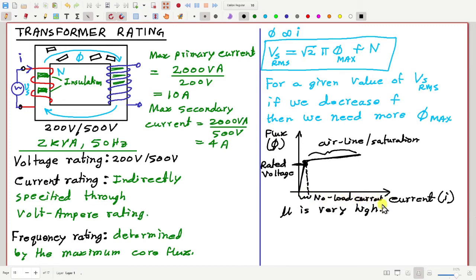So a transformer is designed to have a very high permeability. Initially this graph is very steep, almost vertical, and the voltage rating of a transformer is such that if we apply rated voltage, the flux level will correspond to this value, and the current that the transformer will draw will be this much. This is a very small amount of current because this graph is almost vertical. So no load current is very small.